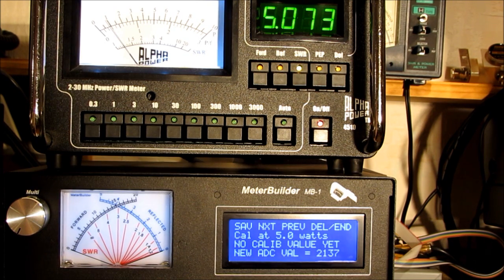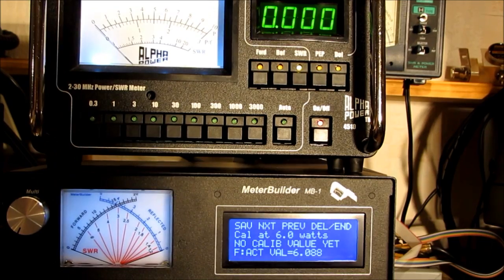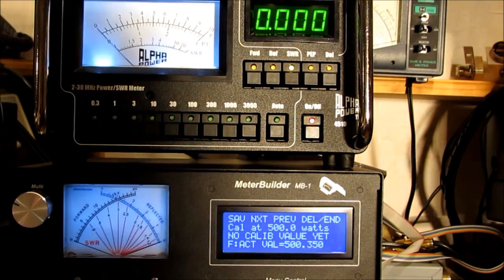Let me go ahead and hit the save button. So you can see the procedure is basically walking through the different calibration points, setting up the power using your transmitter and a reference like the alpha or any other accurate reference you happen to have, and saving the calibration points one at a time. Now I'm going to do a number of calibration points offline so this doesn't get tedious. I'll be back when I've finished the majority of them.